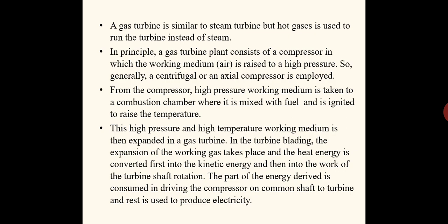In the turbine blading, the expansion of the working gas takes place and the heat energy is converted first into kinetic energy and then into work of the turbine, or shaft rotation. Part of the energy derived is consumed in driving the compressor. I have already told you that almost 1/3 of the power produced by the shaft of the turbine is utilized for running the compressor. The remaining 2/3 is available for the useful work output, or to produce electricity. Okay, that is all about the working.